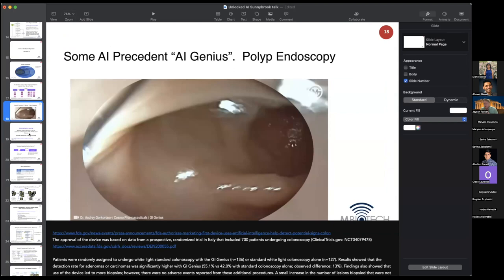Typically right now, a lot of systems using artificial intelligence are being approved through a 510-K or de novo submission. The de novo submissions being used actually have significant clinical data — in some cases up to 700 patients of clinical data for a de novo submission. That's a lot. And it's good to see significantly more disclosure around testing for devices using artificial intelligence for lesion or abnormality detection.